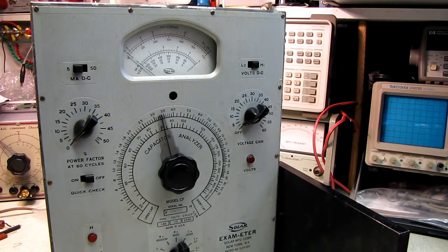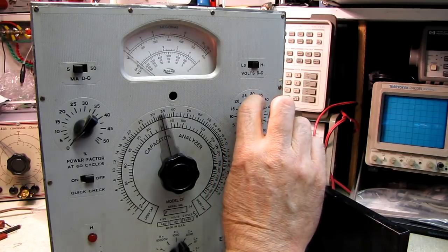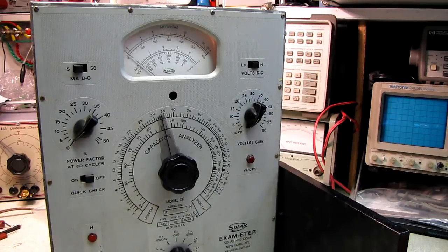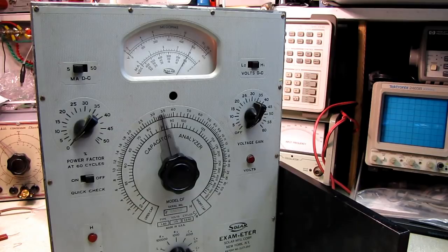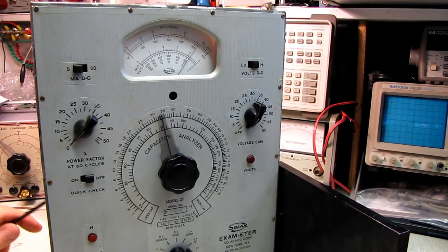And come on, where's the plug? Okay, we're plugged in. Dial lights are on, and I'm going to crank the voltage all the way up. I'm going to put this on M times 1. And as this warms up, we should see an upscale reading here. And I'm going to need an insulated diddle stick. Okay, we've got our insulated diddle stick so that we don't get fried in case the potentiometer shaft is hot.